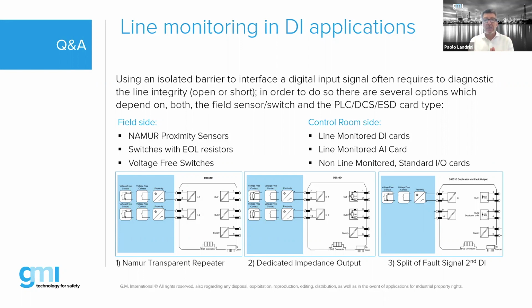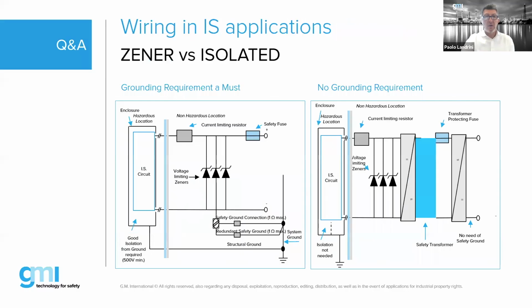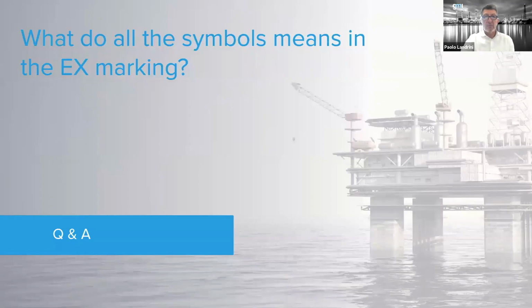So for example, some DI cards can read this information correctly, some cannot, because they look for an open circuit above 30, 40 milliamp, and an AI barrier will clamp at 22 milliamp, so they can never see an open circuit. But it's a combination between the field device, the barrier, and the analog or digital input card that you're going to use. Okay, let's move forward.